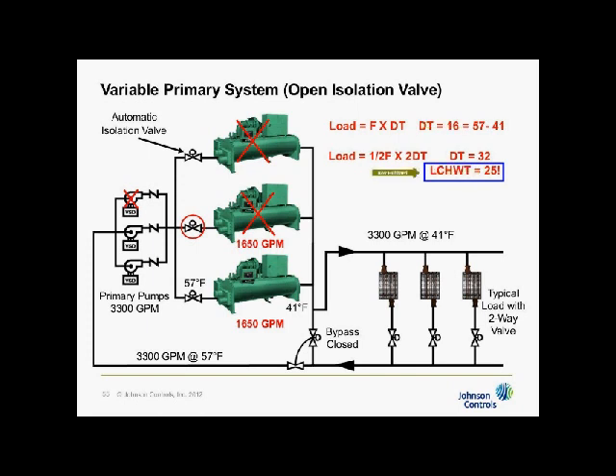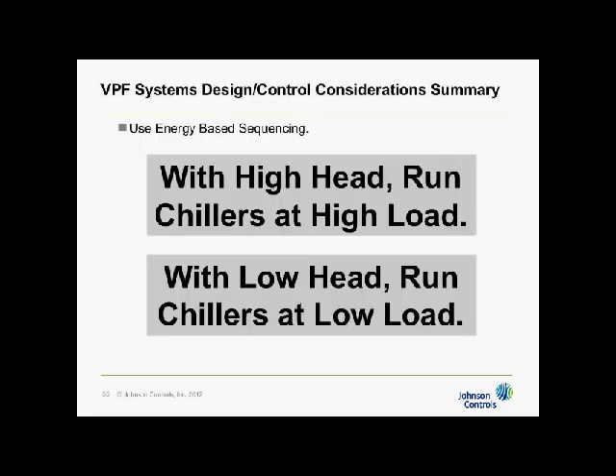Okay? So 25 degrees, of course, is never going to be reached, because the low water temperature cutout is going to kick out 4 degrees below set point, standard. So my 40 degrees, when it gets to 36, off she goes. And you can imagine what a nuisance that is when you have this chiller running. You just want to add the second one, and this one trips off on you. It all happens because this valve that's here is two-position, and just opens in 10 or 15 seconds. This is why I said earlier we need modulating valves to open up over the course of 1.5 to 2 minutes. Okay? That way it solves that problem. This opens as fast as the vanes close and the problem goes away. Okay?